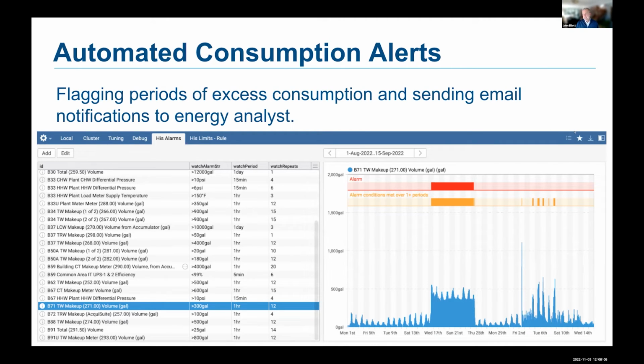So you can see on the right, here's an example where you could have several cases where you actually exceed the threshold, but because it doesn't happen continuously, we don't want it to trigger an alarm, and we only want it to trigger an alarm when you have a case where you've had a certain number of exceedances over a certain period. So this is one little strategy to sort of clean up the alarms, and we're building this up over time. And it's proven very useful to identify a lot of water waste that occurs, but also in other systems as well. And we can respond quite quickly to this.